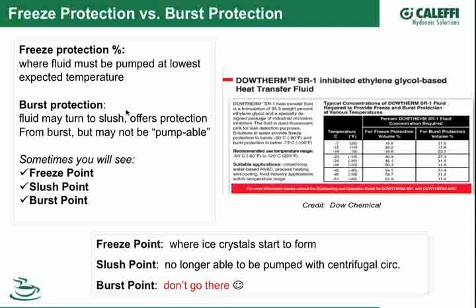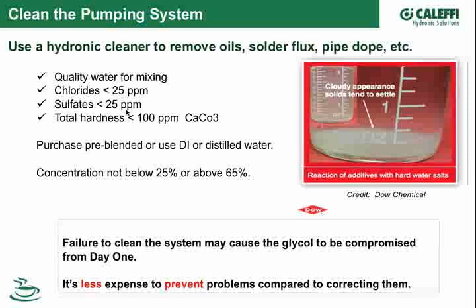The other biggest mistake I've seen in the industry is not having a clean system when you put glycol in. Even brand new pipe off the shelf can have thread cutting oils, flux, or residue from extrusion or assembly, whether it's iron pipe or a boiler with lubricants and oils. Even a brand new system should have a cleaner run through it first, because you can ruin the glycol the very first day if the system isn't cleaned properly.